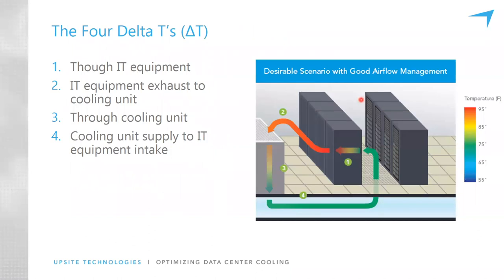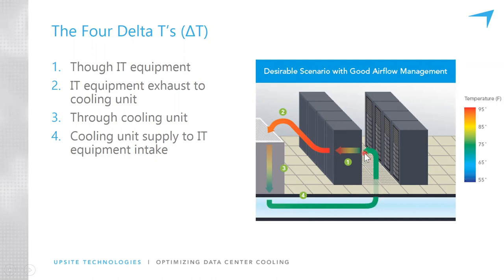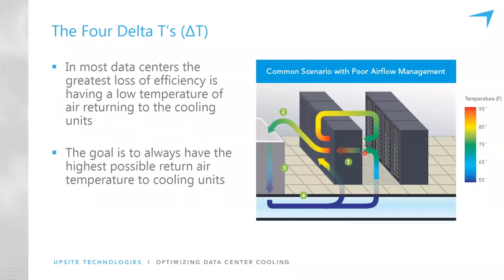I want to share one more concept: the four delta Ts. Most people are aware of two of the delta Ts in a computer room — labeled as one and three on this image. We all know that air warms up as it flows through IT equipment and cools down as it flows through cooling units. There are two more delta Ts that are very important to measure, labeled as two and four, and they can provide insight into the potential for optimizing conditions in the room. This image shows an ideal scenario where we're not seeing much temperature change for delta T two and four, but in typical conditions we're seeing a lot of change.